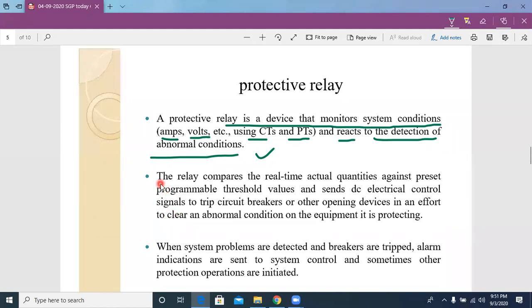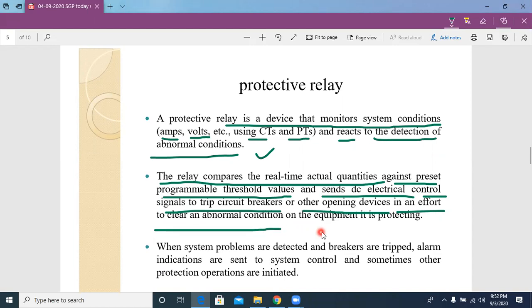Now, one more important thing about the relay is it always compares the real-time actual quantities against preset programmable threshold values, and sends DC electrical control signals to trip circuit breakers or other opening devices in an effort to clear an abnormal condition on the equipment it is protecting.